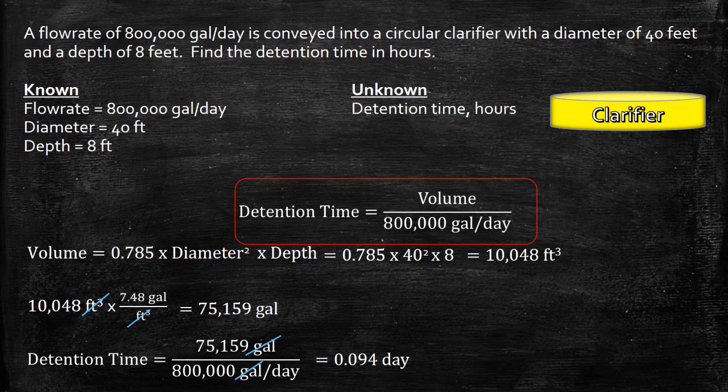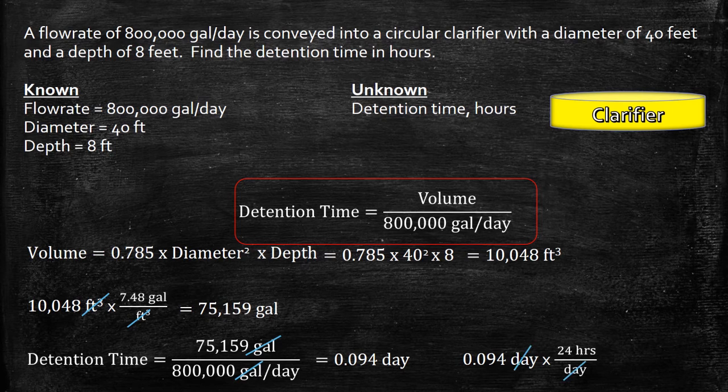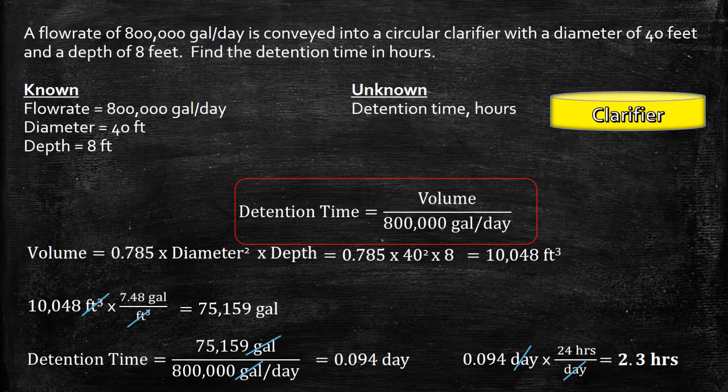So let's make that conversion one last step. 0.094 day multiplied by the conversion factor, 24 hours divided by 1 day. The days cancel out. Using our calculator, we get 2.3 hours as the detention time of the circular clarifier.